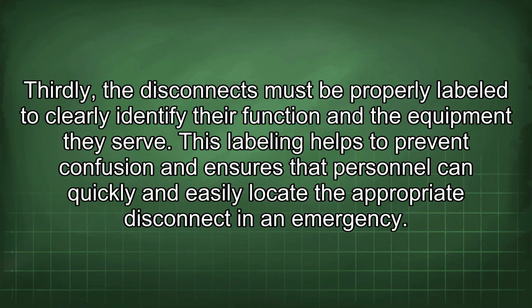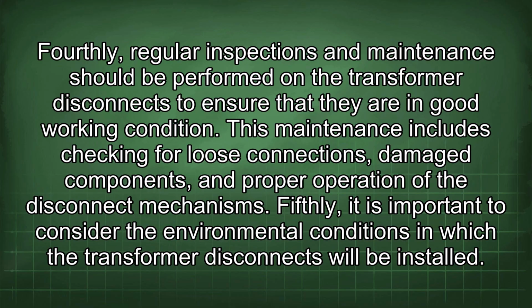Thirdly, the disconnects must be properly labeled to clearly identify their function and the equipment they serve. This labeling helps to prevent confusion and ensures that personnel can quickly and easily locate the appropriate disconnect in an emergency. Fourthly, regular inspections and maintenance should be performed on the transformer disconnects to ensure that they are in good working condition. This maintenance includes checking for loose connections, damaged components, and proper operation of the disconnect mechanisms.